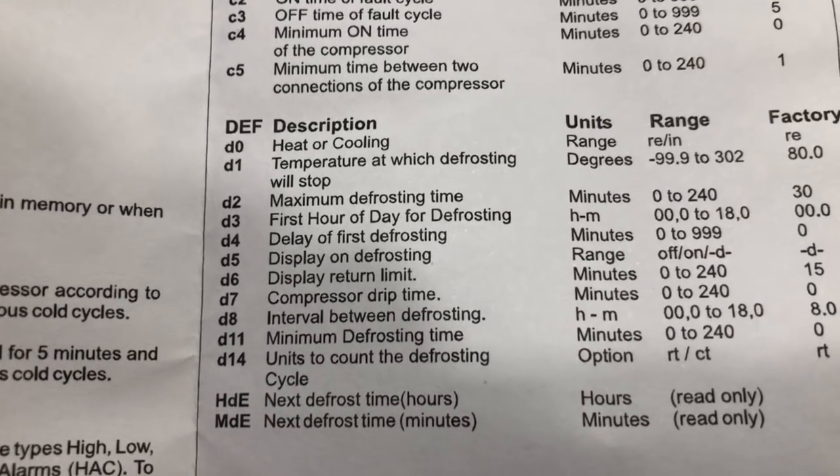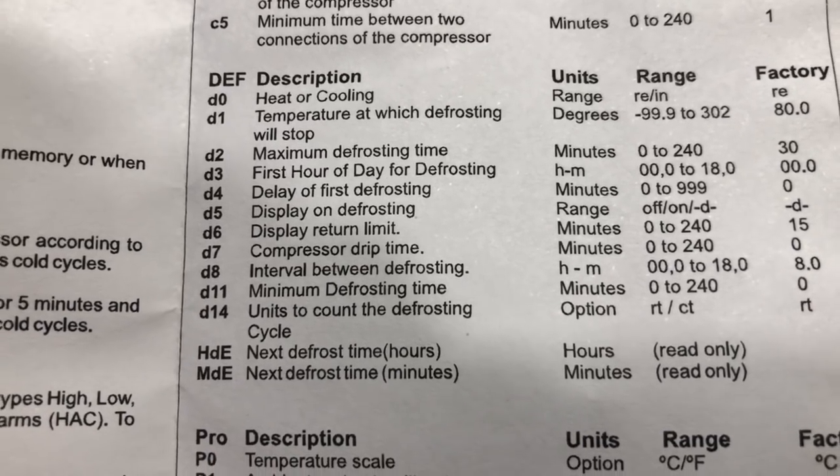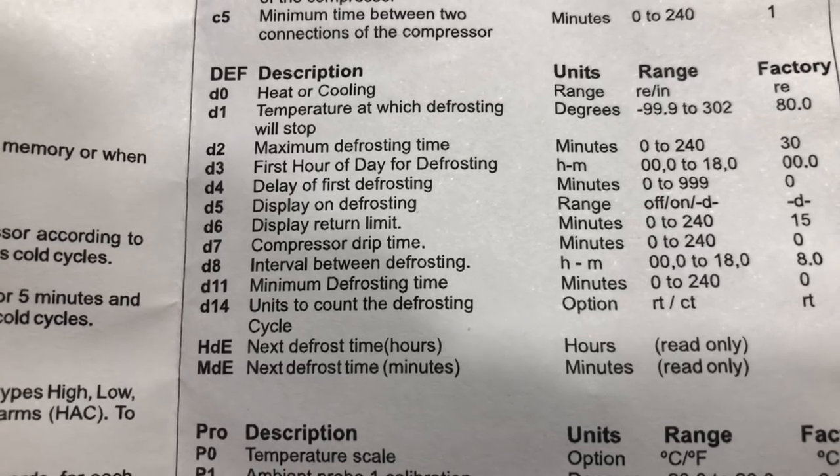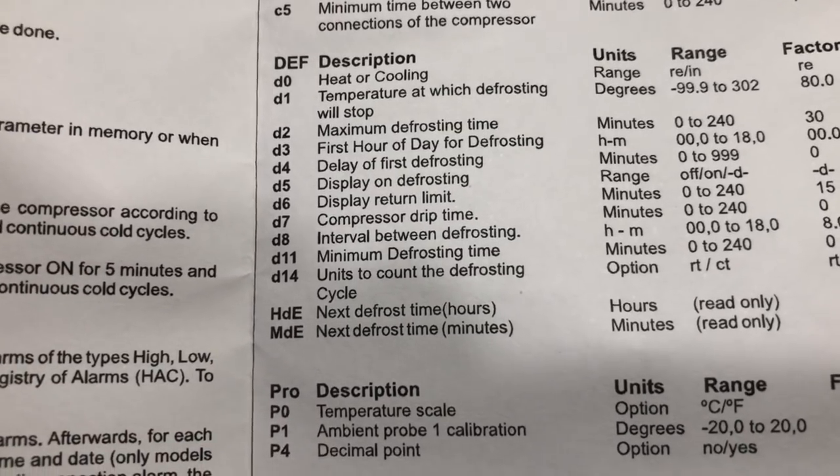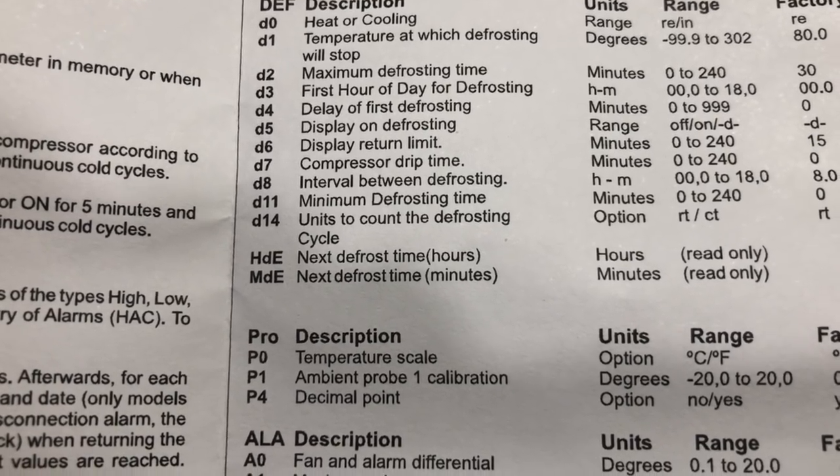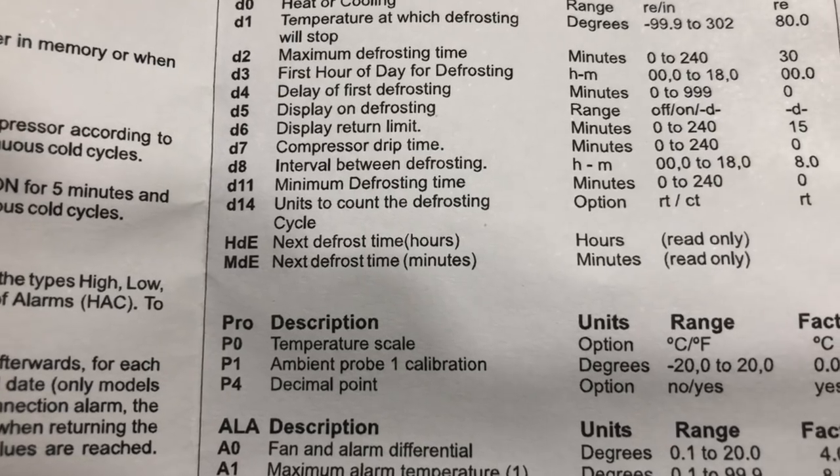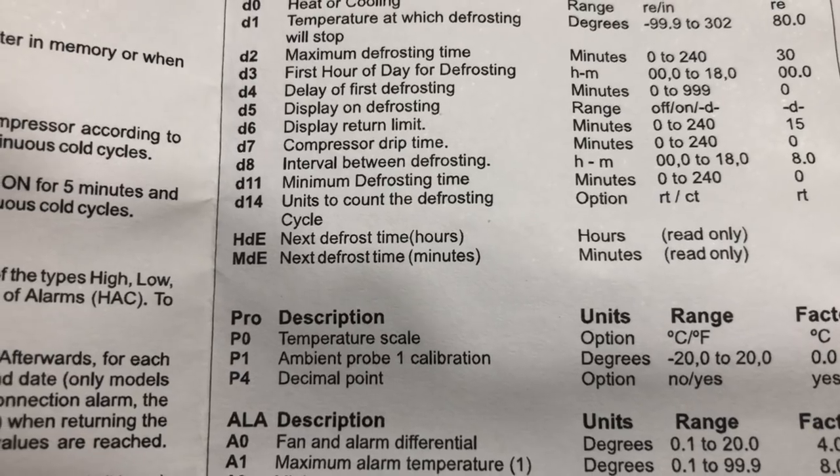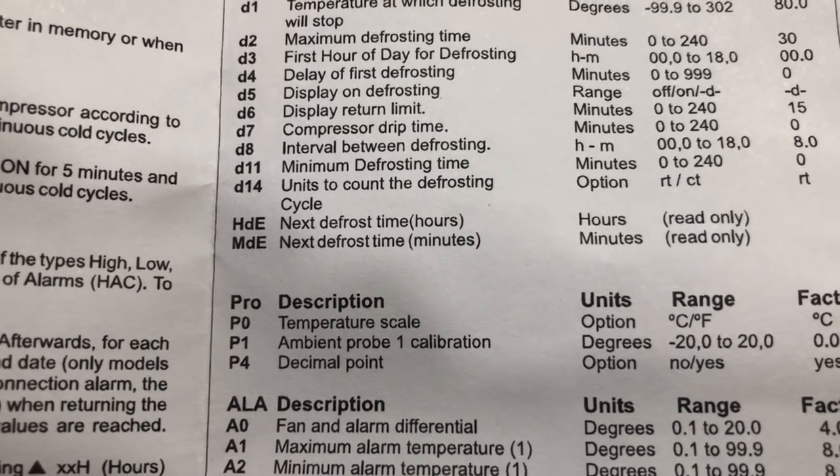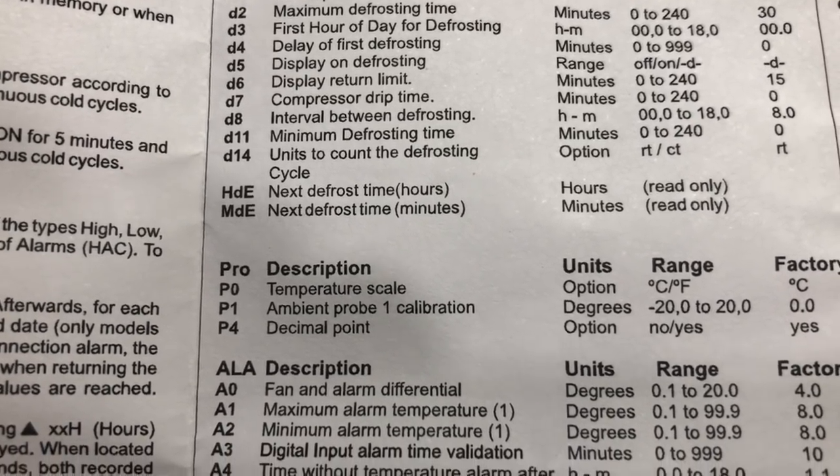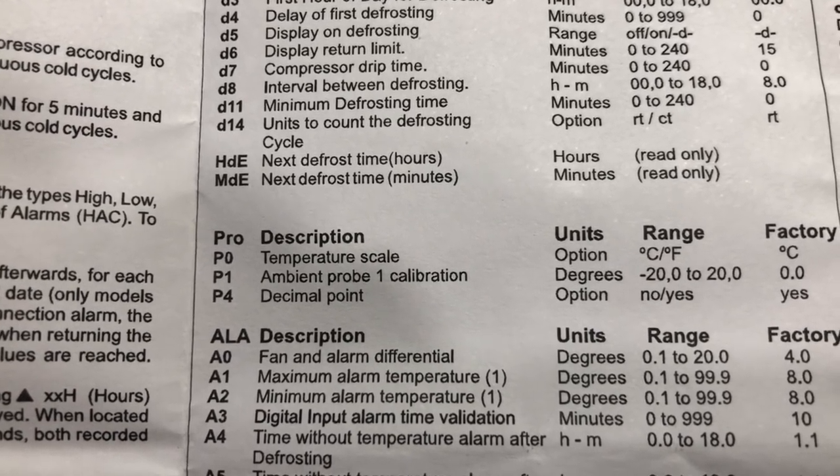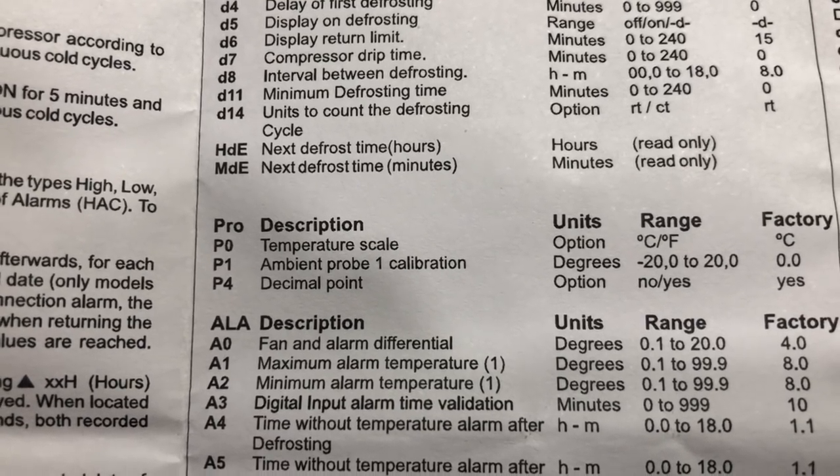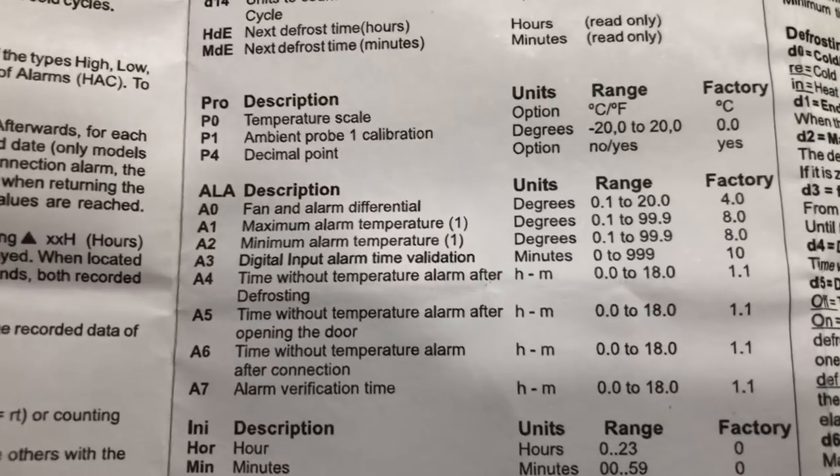Then you get into your defrost. This is really cool. It'll do what the Dixell does. You can have it heating or cooling, temperature at which defrost will stop. So that's your defrost termination temperature. Maximum defrost time, first hour of the day for defrosting, delay of first defrosting, display on defrost. So you can have it freeze the temperature when it went into defrost to trick your customer, or you can have it show the actual temperature while it's defrosting. Display return limit, compressor drip time, intervals between defrosting, minimum defrosting time, units to count the defrosting cycle, next defrost hour, next defrost in minutes.